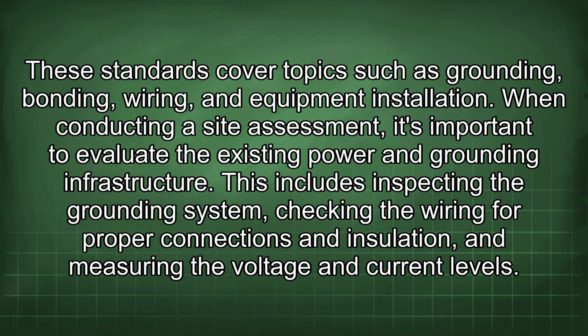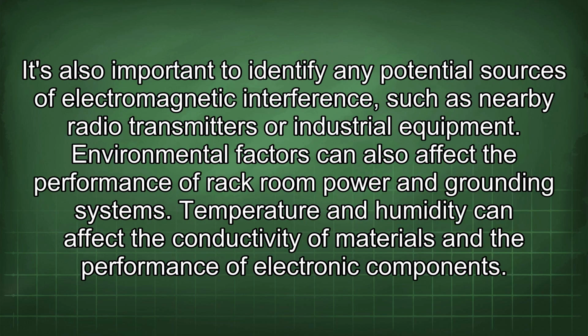When conducting a site assessment, it's important to evaluate the existing power and grounding infrastructure. This includes inspecting the grounding system, checking the wiring for proper connections and insulation, and measuring the voltage and current levels. It's also important to identify any potential sources of electromagnetic interference, such as nearby radio transmitters or industrial equipment.